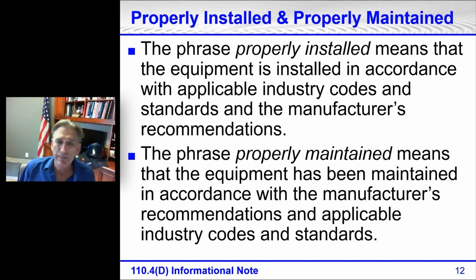The phrase properly maintained means that the equipment has been maintained in accordance with the manufacturer's recommendations and applicable industry codes and standards. Not all pieces of equipment have maintenance or recommended maintenance requirements. For example, a plain panelboard or plain breaker does not have any type of manufacturer's recommendations as far as testing or anything.